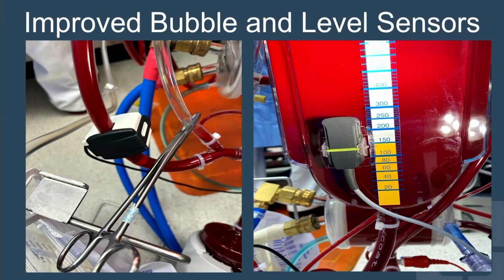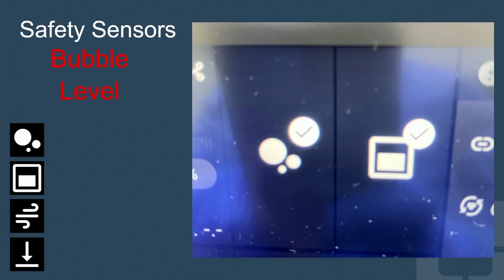The bubble alarm detects the equivalent on an S5 of medium bubbles. The level detector requires a sticker. The sticker technology upgrade here is in the level sensor and no longer in the pad. So here's a pic of what the alarms look like, and the bubble is on the left and the level is on the right, and the check mark means they are activated.